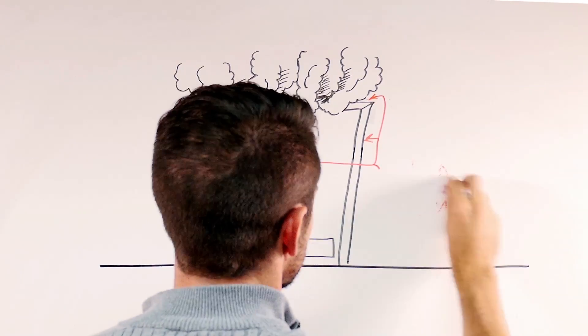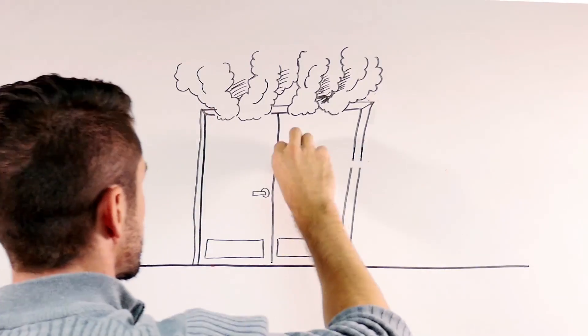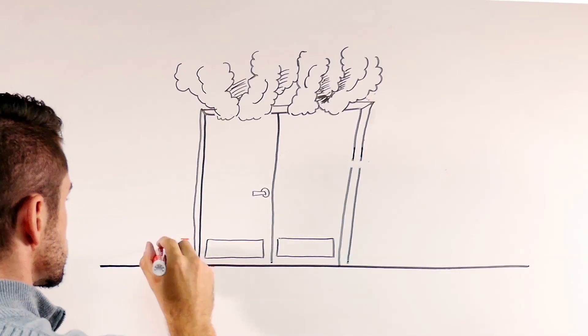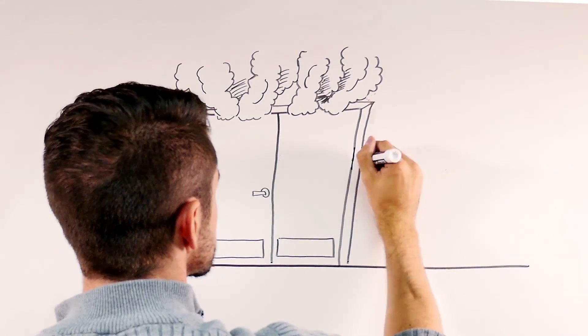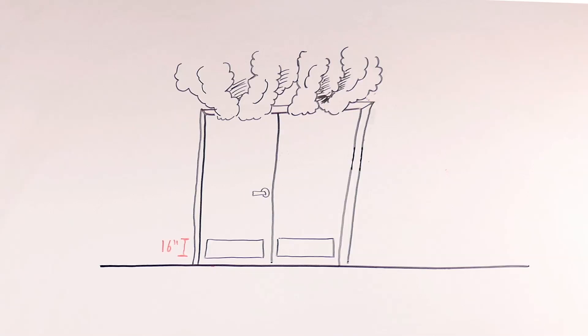Protection plates on fire doors can be installed on the bottom 16 inches of a fire door, but larger plates could affect the performance of the door during a fire. Plates that extend above the 16 inch area must have a label indicating that they are acceptable for use on a fire door.